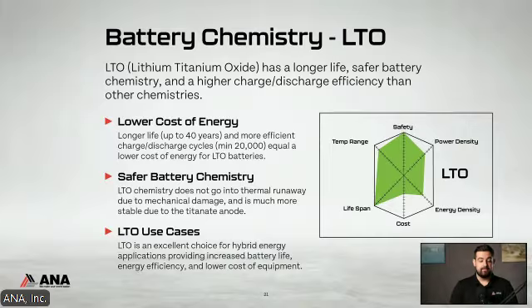It's a very safe battery chemistry. It's very difficult to induce thermal runaway on an LTO battery or module. You usually have to try multiple different levels of failure to get LTO to set off. LTO is an excellent choice for hybrid energy systems, with increased battery life, and it's very energy efficient. But one trade-off is that it is a little more expensive than, let's say, an LFP battery.